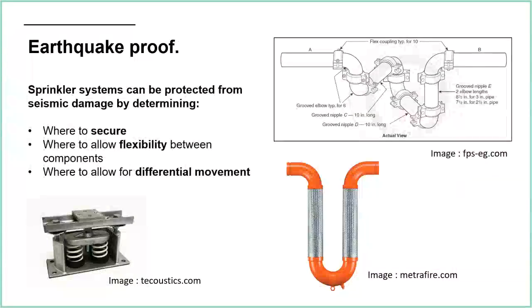Those images show other ways of increasing flexibility. On the left-hand side, things using spring-loaded or dampened equipment again just help to absorb some of that impact. The image on the top right is essentially putting a load of extra bends in, for no other purpose than for when there's an earthquake and things are moving - it helps absorb the impact. Some of those joints can twist and move and pull apart, rather than having one long length of pipe. From a frictional loss point of view that's a bad idea, but from an earthquake point of view it's a good idea.